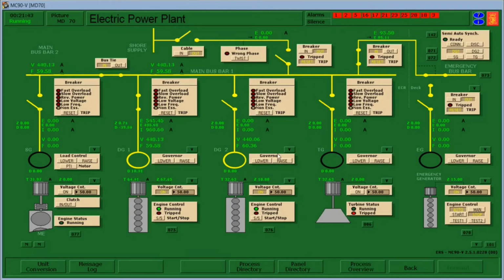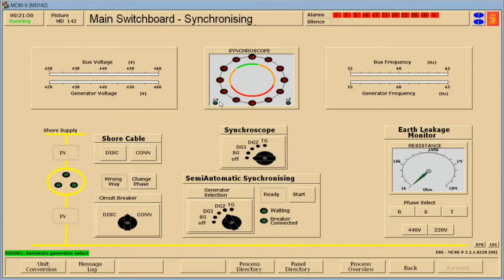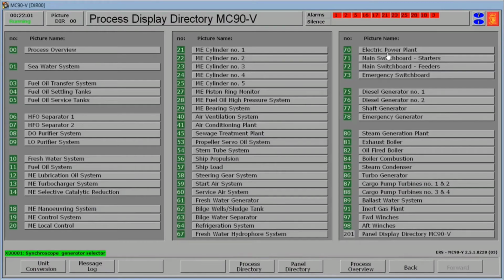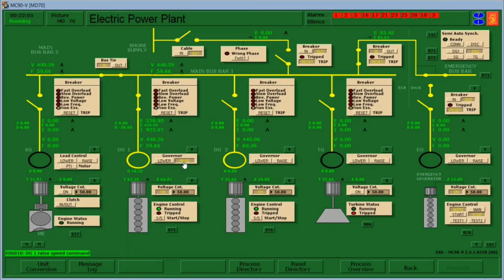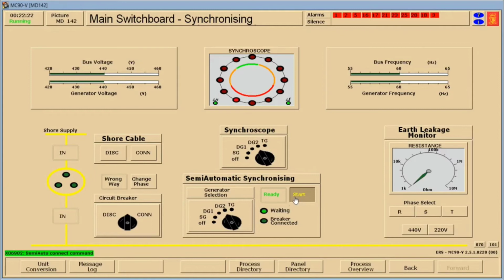Electric power plant. Now we synchronize our two generators. So click diesel generator number 2, synchroscope. So we must increase the governor. We must raise. Okay, start our semi-automatic synchronizing. So when the indicator reaches 12 o'clock, it will now synchronize. Okay, so our two generators are now synchronized.